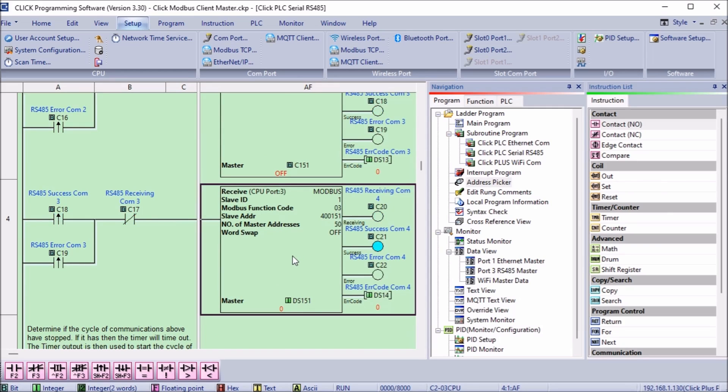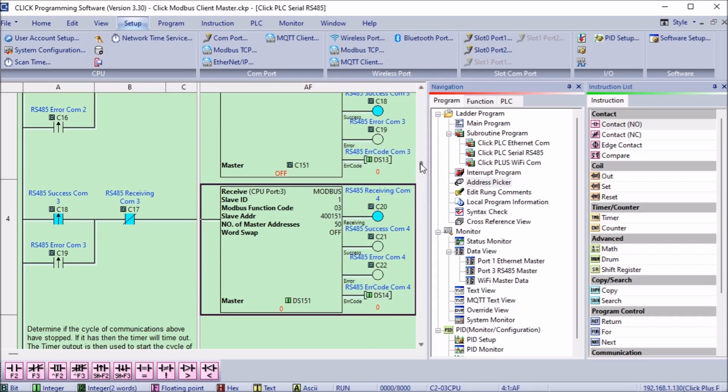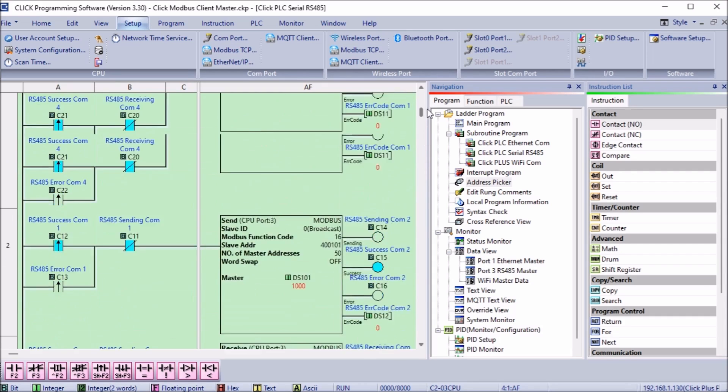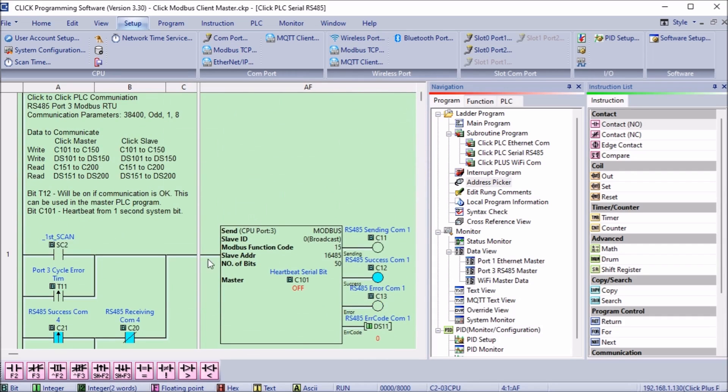We will read 50 registers starting at 400151 address DS151 of the slave PLC and write them into the master PLC at DS151. The output flags of this instruction will trigger the first send instruction again.